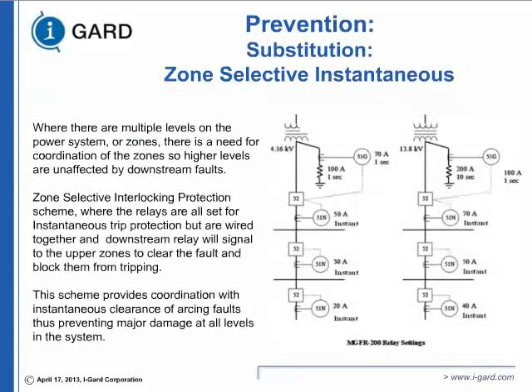Optical detectors and zone selective interlocking, again, you can do that with your relays also. Of course, now you're depending on time-based coordination. You can see that time goes up or the setting goes up, as opposed to zone selective, where the devices talk to each other, are interlinked, and it protects automatically.